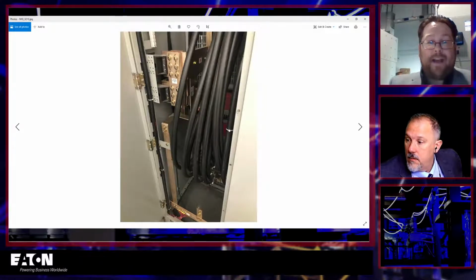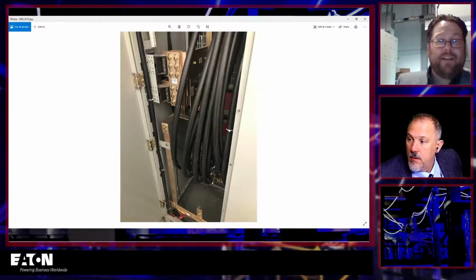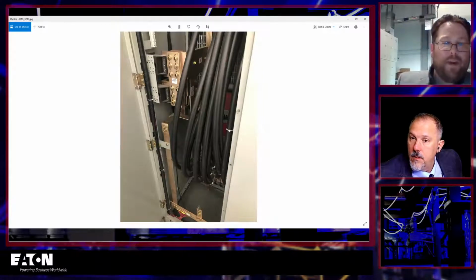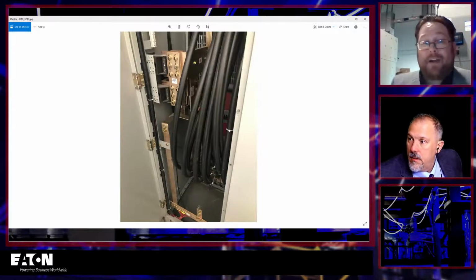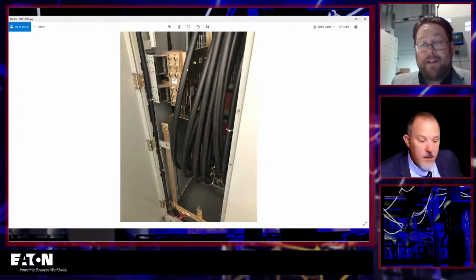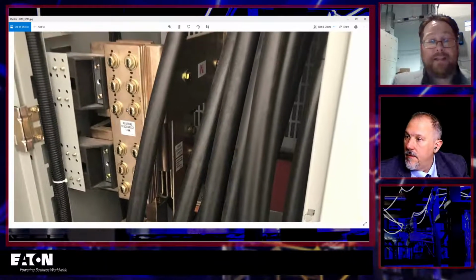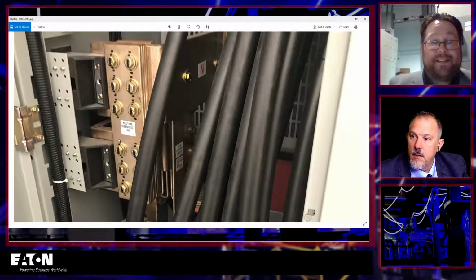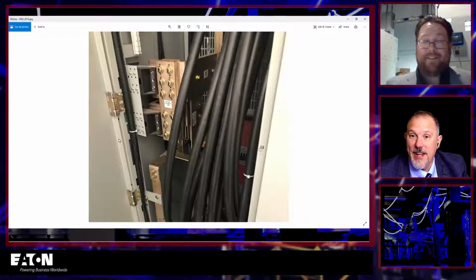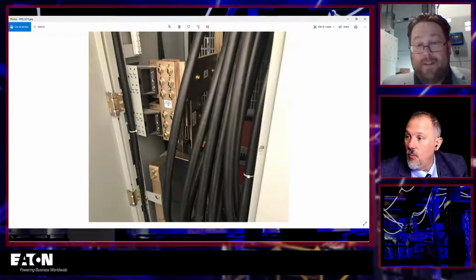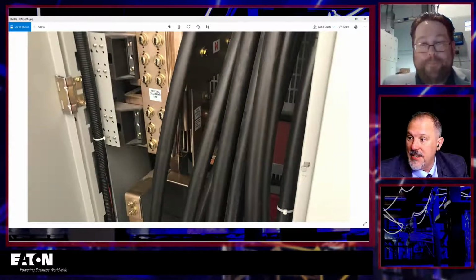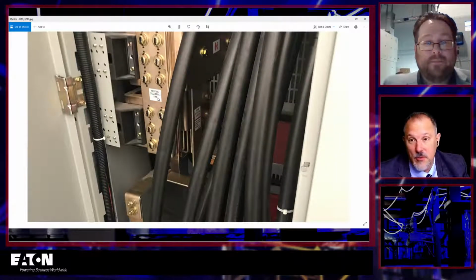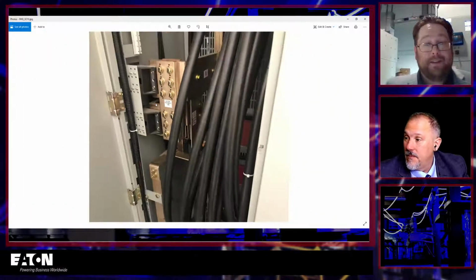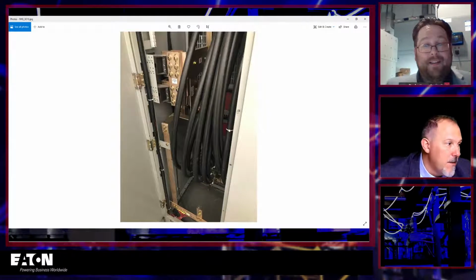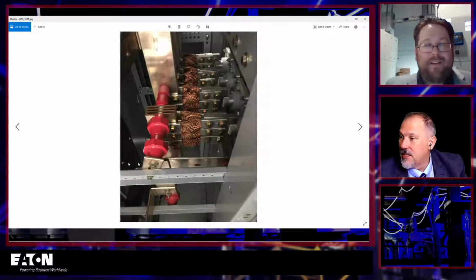That's right. This is actually the other end of that exact same switchgear, and right where the one hinges near the top of the picture, Tom, where the white sticker is on the bus bar. That's the actual neutral to ground bond inside of the switchgear. Okay. So the right and the left of the switchgear are actually different. Wow. So you really got to know what you're looking at to understand what that linkage is, what this bar right here. It says neutral disconnect, but you could have two of these in there, right? You could, absolutely.